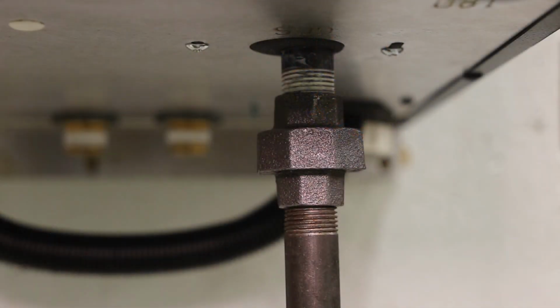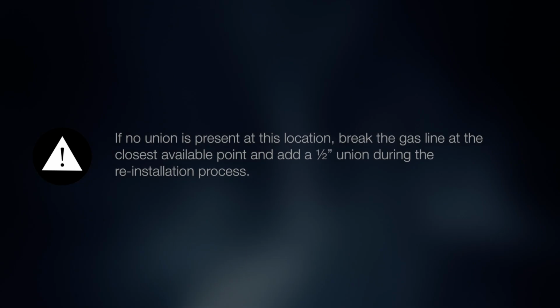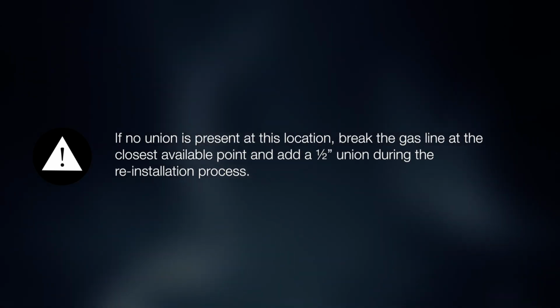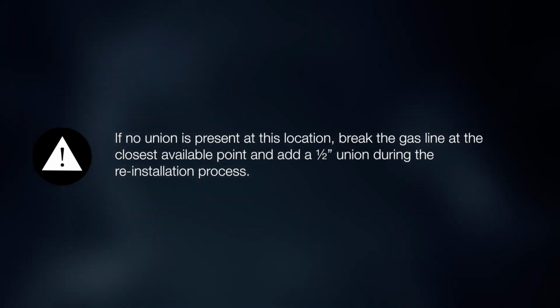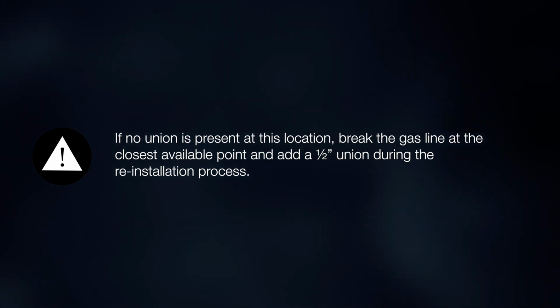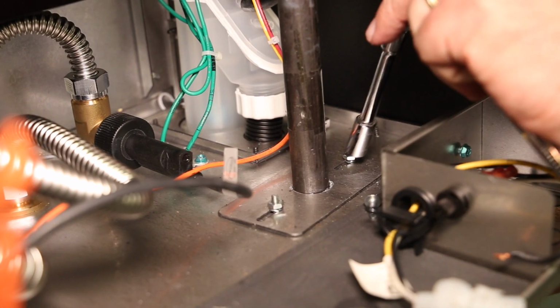If the gas piping is already installed, a 1/2-inch union may be installed directly under the boiler. If this is the case, secure the top half of the union with an adjustable wrench, and loosen the bottom half of the union with a second adjustable wrench. If no union is present at this location, break the gas line at the closest available point and add a 1/2-inch union during the reinstallation process. Remove the 2 bolts and nuts holding the gas line sealing plate to the bottom of the boiler chassis.